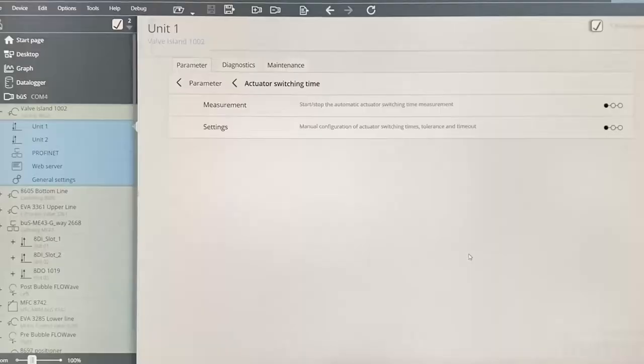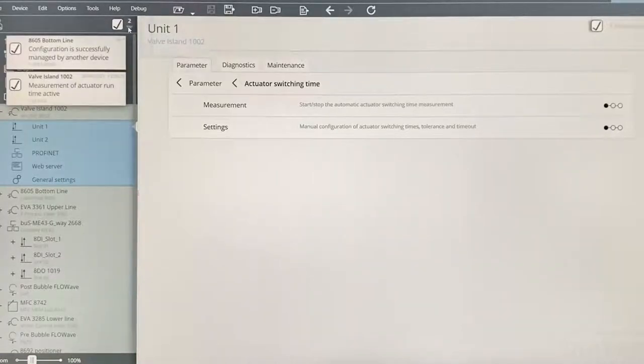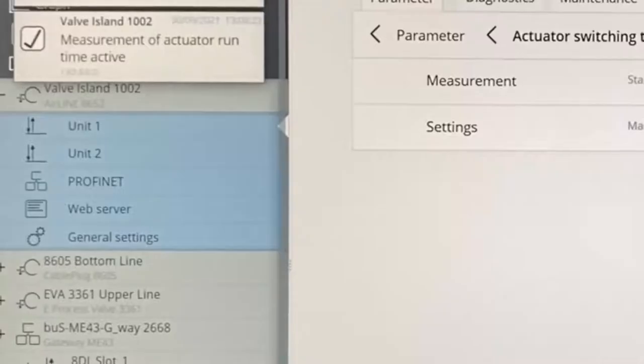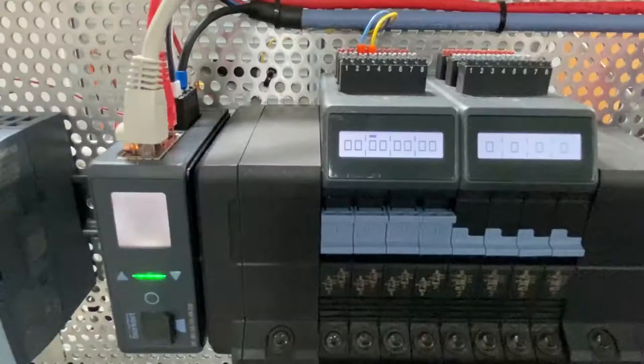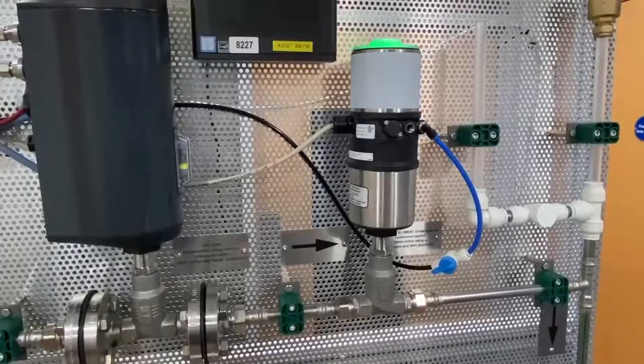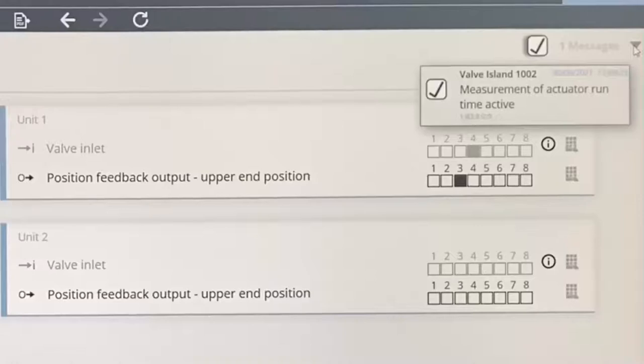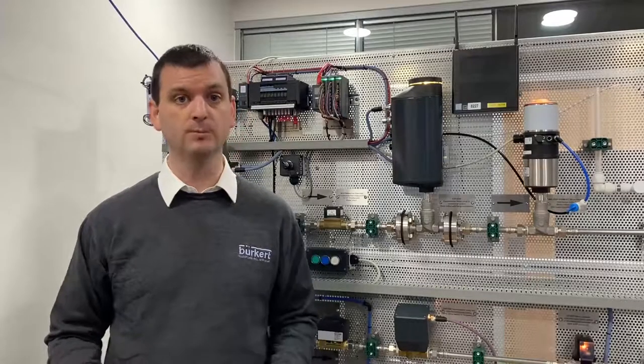You will now notice on the Communicator software a notification appears in the top left. On selecting this, you will see that it is confirming that the measurement of actuator runtime is active, and the system will now monitor the time it takes for the pilot valve to open to receiving a feedback signal. After 20 cycles, the notification will disappear and the setup will be done.